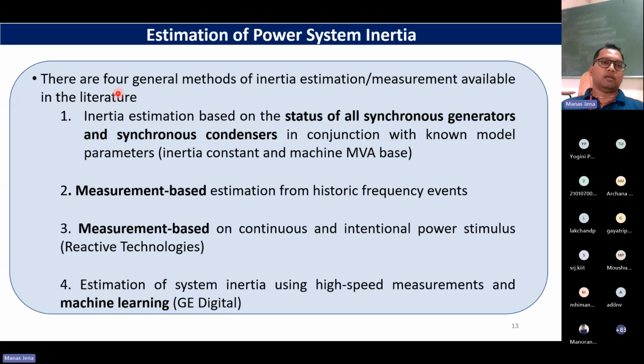But in general, there are 4 methods for these estimations. Inertia estimation based on status of all synchronous generators and synchronous condensers. If we have the status information, maybe through SCADA, then we can estimate the inertia roughly, or we can do inertia estimation based on the measurements. In our grid, a lot of measurements are coming, especially through the phasor measurement units, PMUs, synchrophasors. So can we pick up some events and, using the PMU data, estimate the system inertia? I think this is also being tried in our Indian grid, Indian control room.